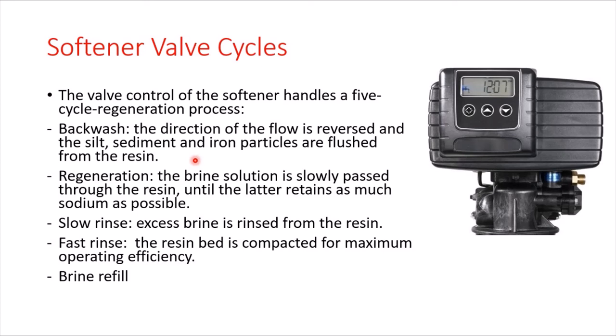The second process is regeneration, where the brine solution is slowly passed through the resin until the resin retains as much sodium as possible. The third step is the slow rinse, where the excess brine is rinsed from the resin. Then we have the fast rinse, where the resin bed is compacted for maximum operating efficiency. Finally, we have the brine refill.